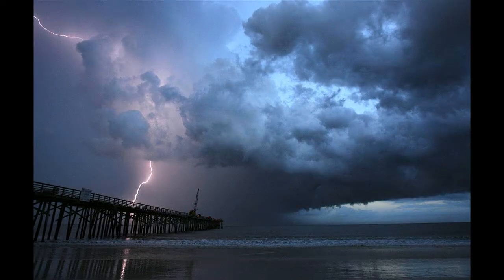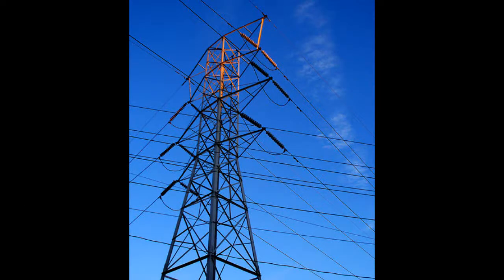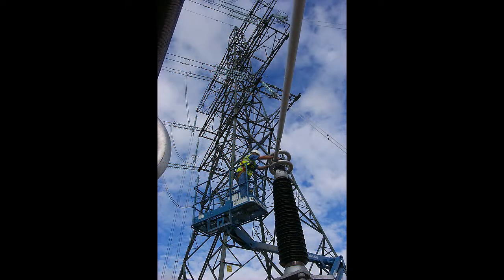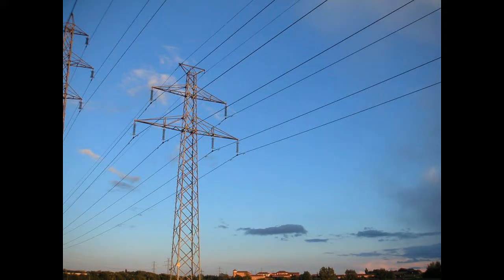That's why scientists and others are working on ways to keep geomagnetically induced currents out of transmission lines to begin with. A device called a capacitor could be installed near each vulnerable transformer to effectively block currents from entering the transmission lines. Capacitors are usually fairly small, the ones on a circuit board inside a typical radio usually smaller than a fingertip. But in transmission systems, the equipment would be roughly the size of a washing machine, and the capacitors would need to be bypassed in a fraction of a second to allow conventional currents through.